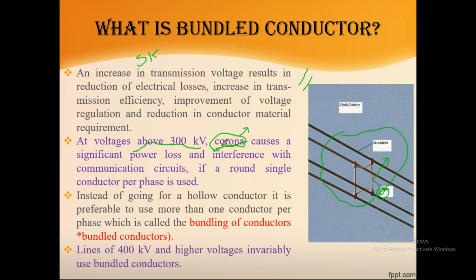So you can also get a question like this: for reducing corona loss, what factors do we have to consider? Options such as if the voltage level increases, the conductor size decreases, or the diameter increases, and so on. It means it completely depends on the diameter of the conductor. Suppose if you use a bundle conductor like this, the diameter will increase.